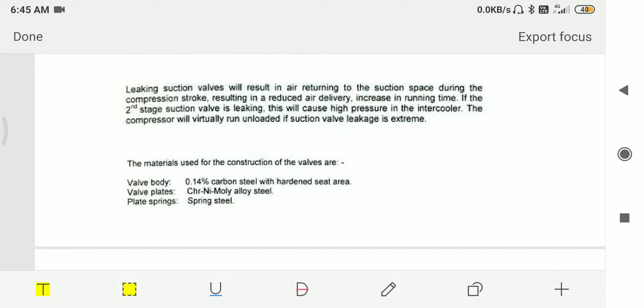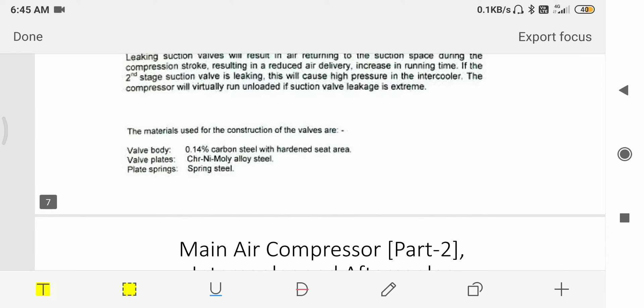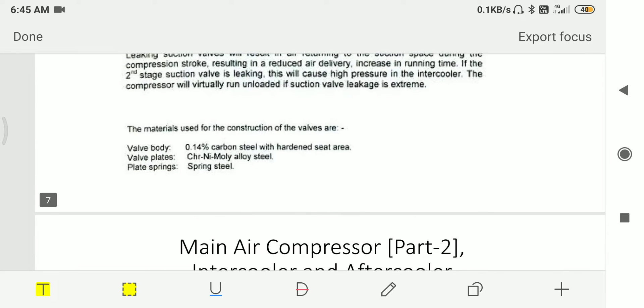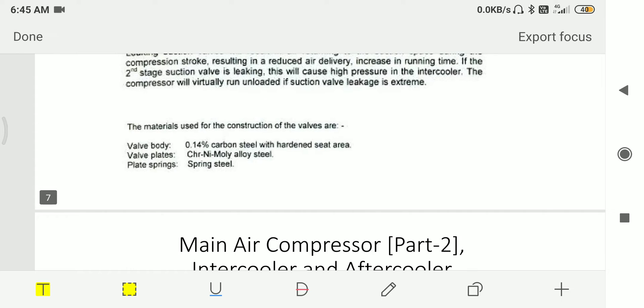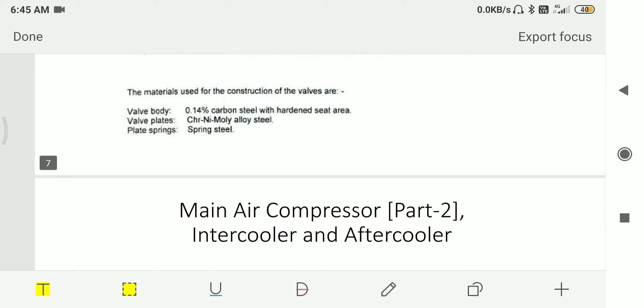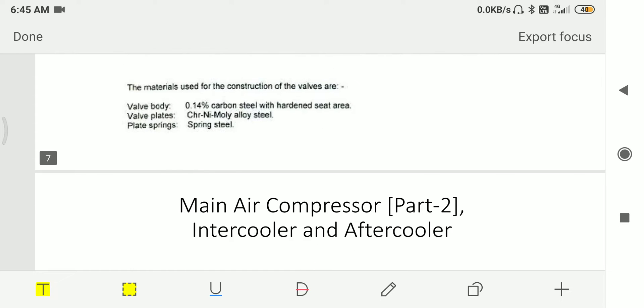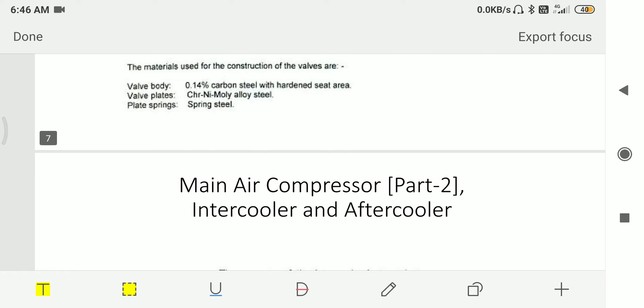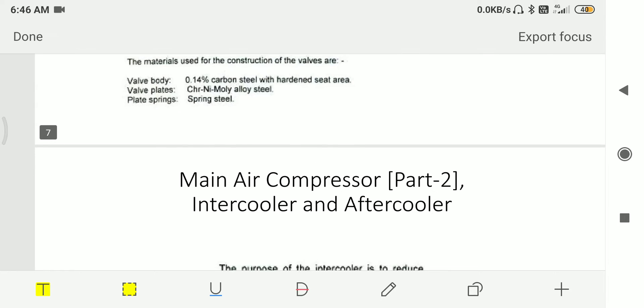If second stage suction valve is leaking, this will cause high pressure in the intercooler. The compressor will virtually run unloaded if the suction valve leakage is extreme. Material used for construction of the valves is 0.14% carbon steel with hardened seat area, but in some books it will say 0.4% carbon steel. Valve plate is made from chromium nickel molybdenum alloy steel, and plate spring is made from spring steel.